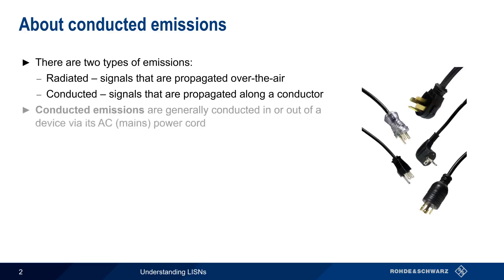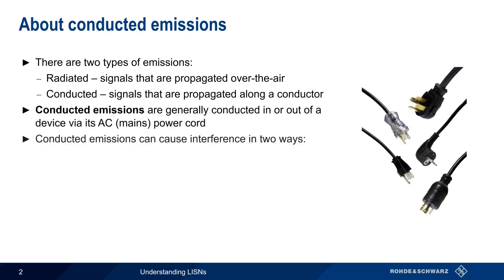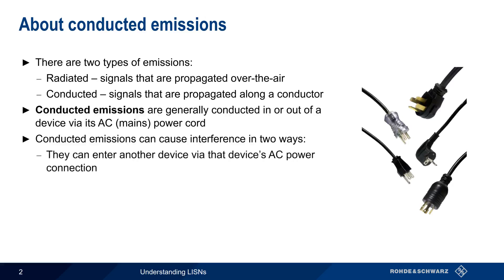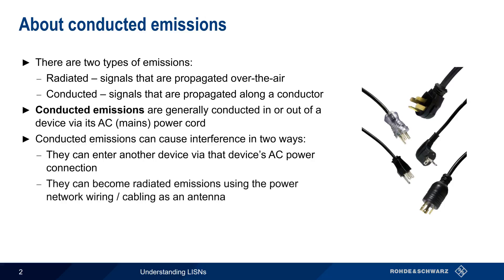In the EMC world, conducted emissions are generally carried in or out of a device via its AC or mains power cord. These conducted emissions can create interference in two ways. First, they can enter another device by being conducted in over that device's AC power connection. They can also be converted from conducted into radiated emissions — for example, when power network wiring or cabling acts as an antenna.